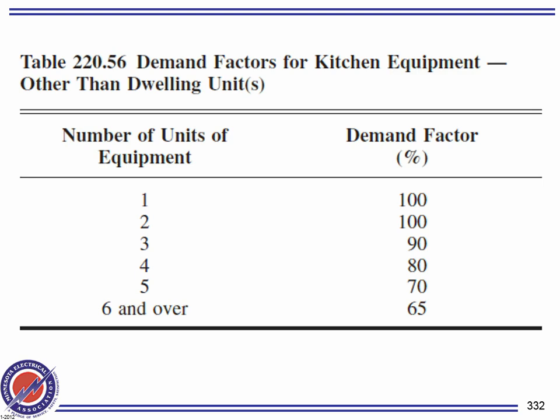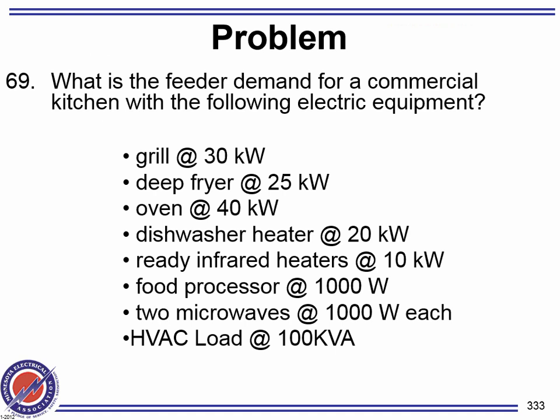So my last question, guys, for the day before I let you loose here. These are non-dwelling, gentlemen. Add them up at face value. If you have 6 of them or over, you apply the demand factor. Okay, so look at these pieces of equipment, please. I have grill, deep fryer, oven, dishwasher, heater, infrared, processor, 2 microwaves.